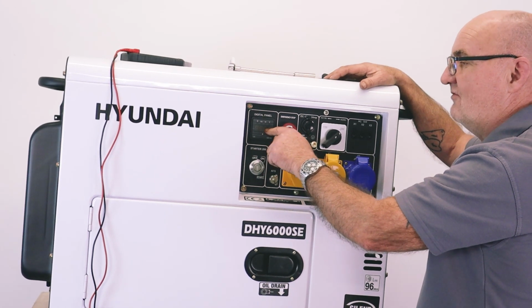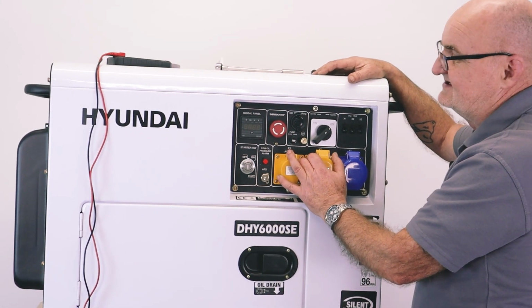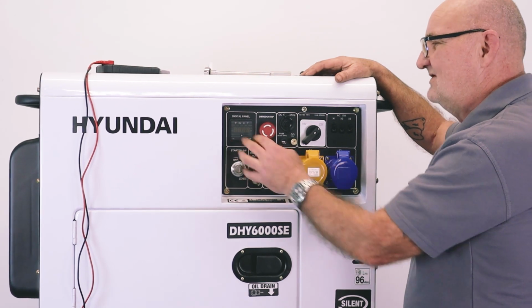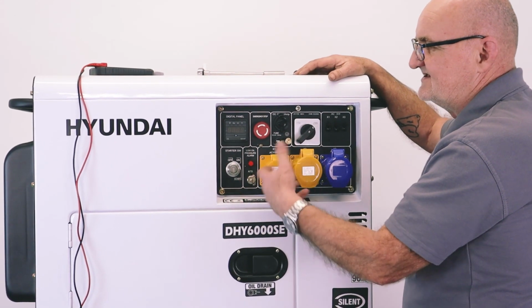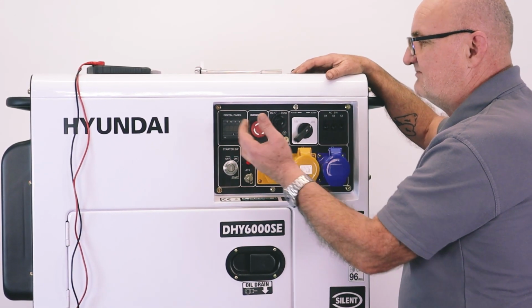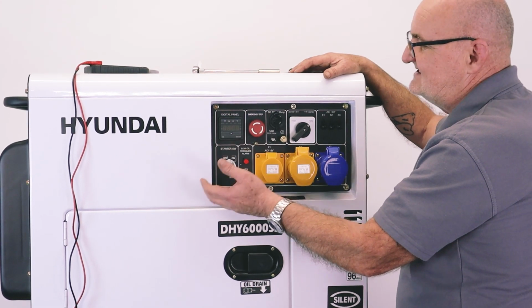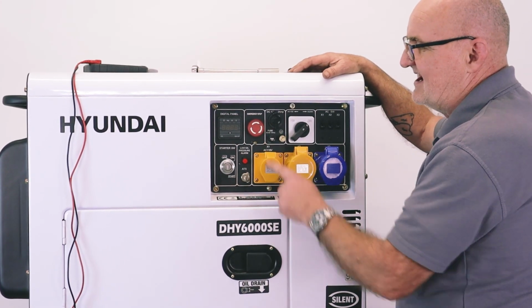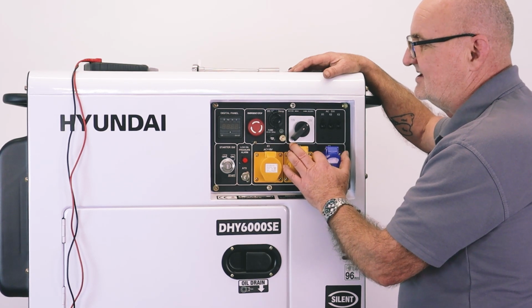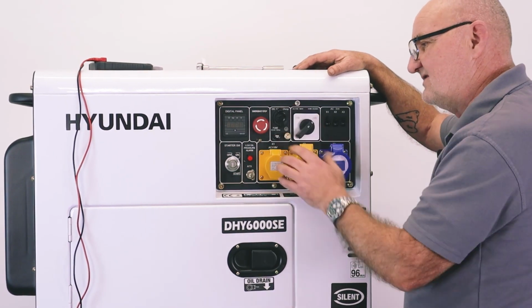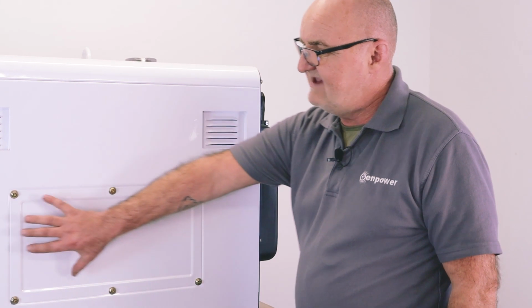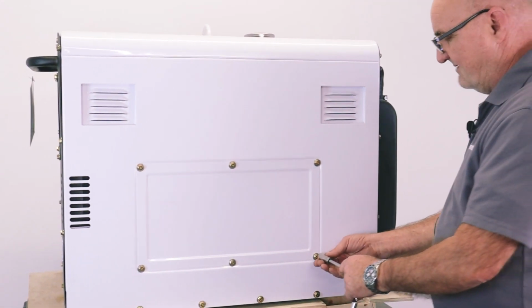If it's got a low voltage on here, maybe 6 volts, something like that, that points us towards an AVR. It tells us the voltage is being produced, but the alternator isn't being excited. So it could be a problem with the AVR. So the next step is to go to the AVR, and that's around the back of the machine behind a panel. So the AVR lives behind this panel on the back.